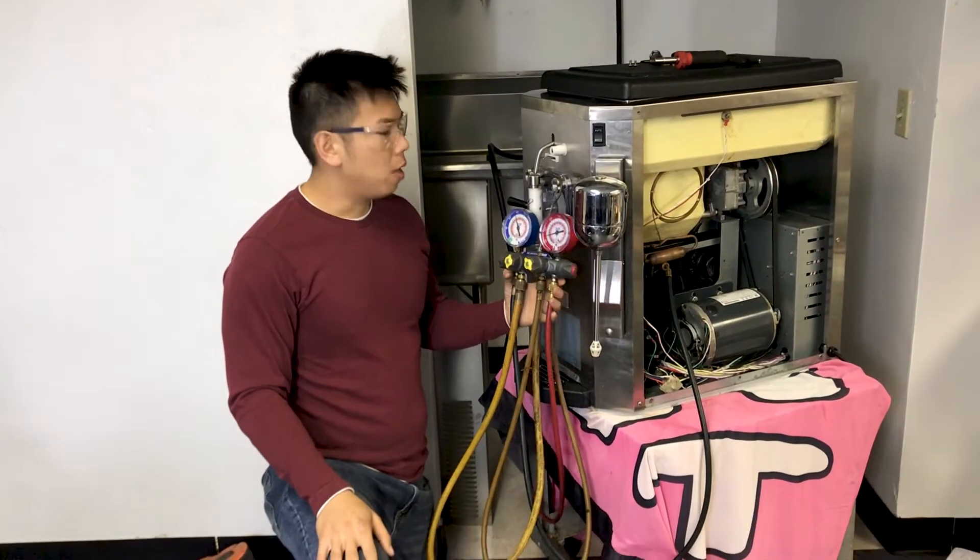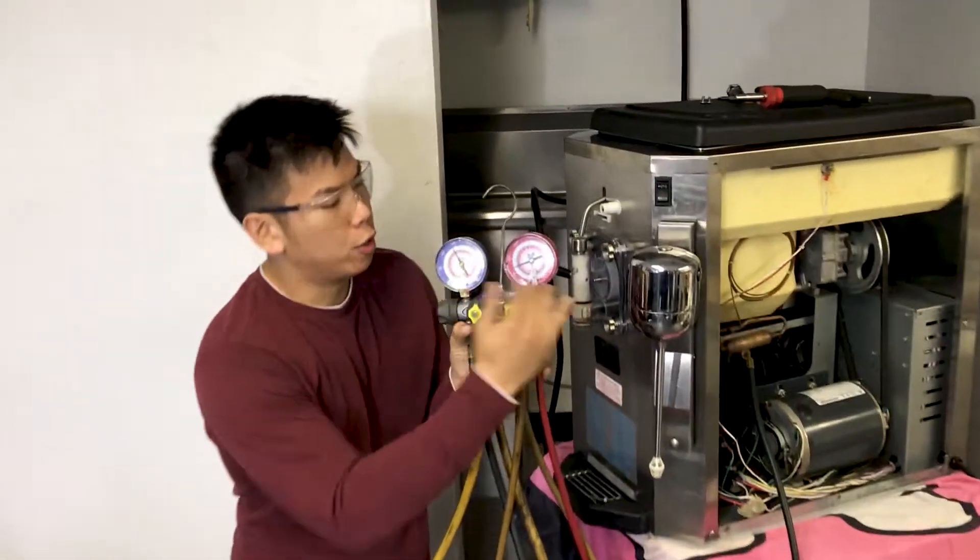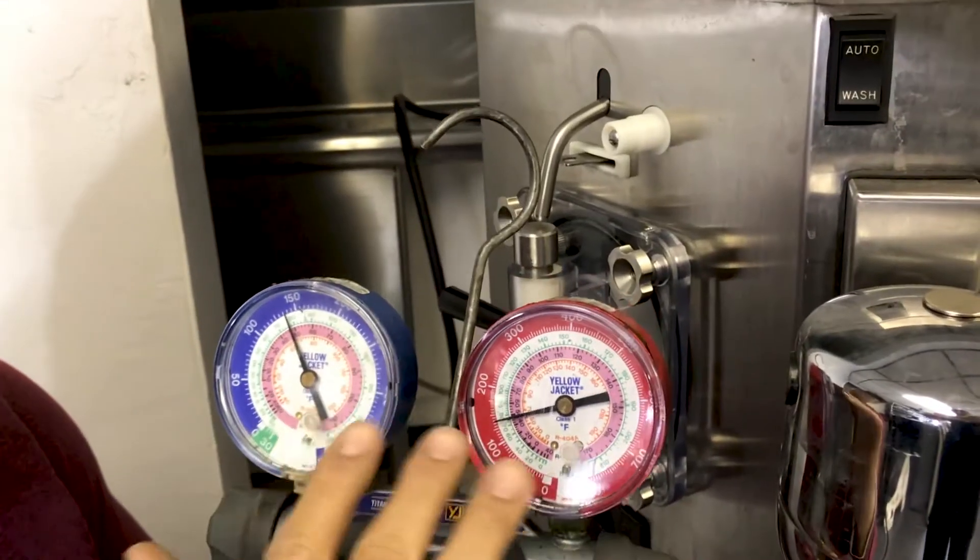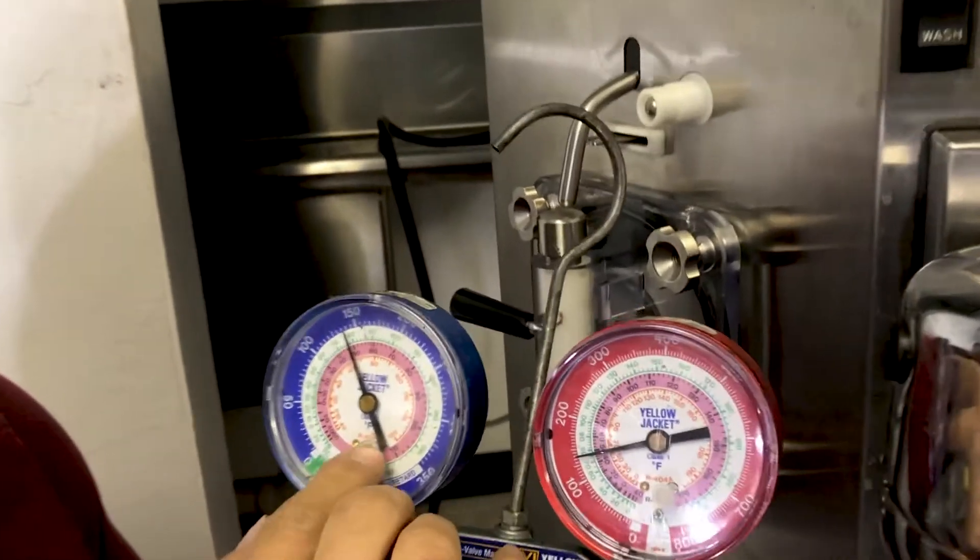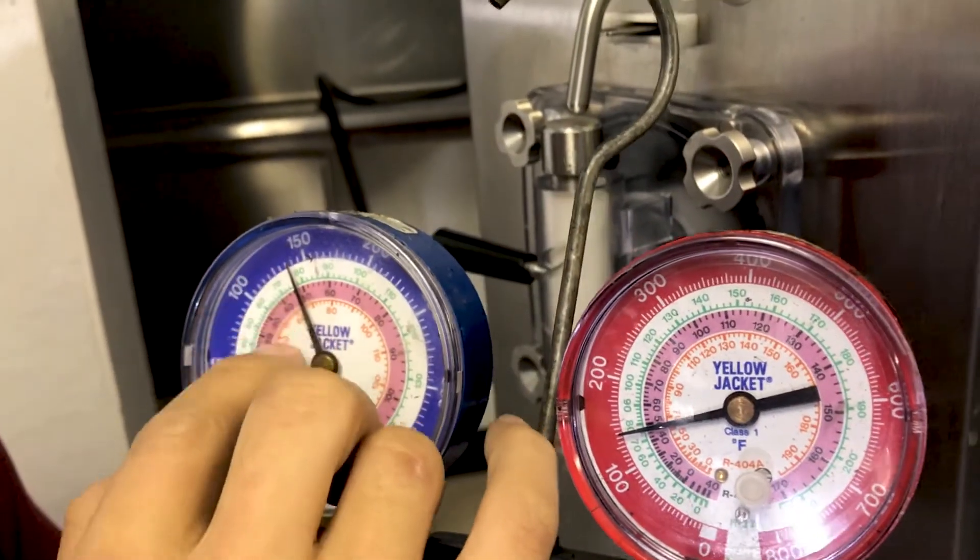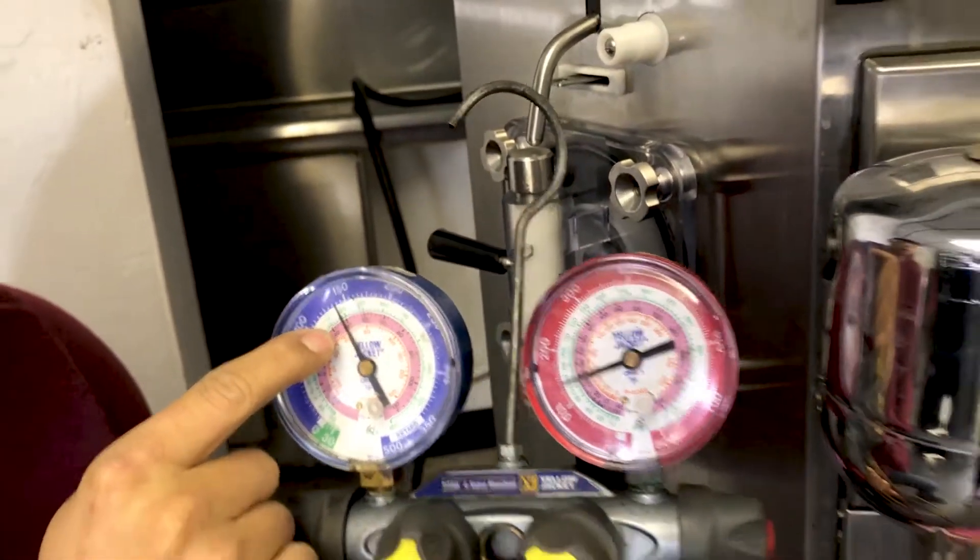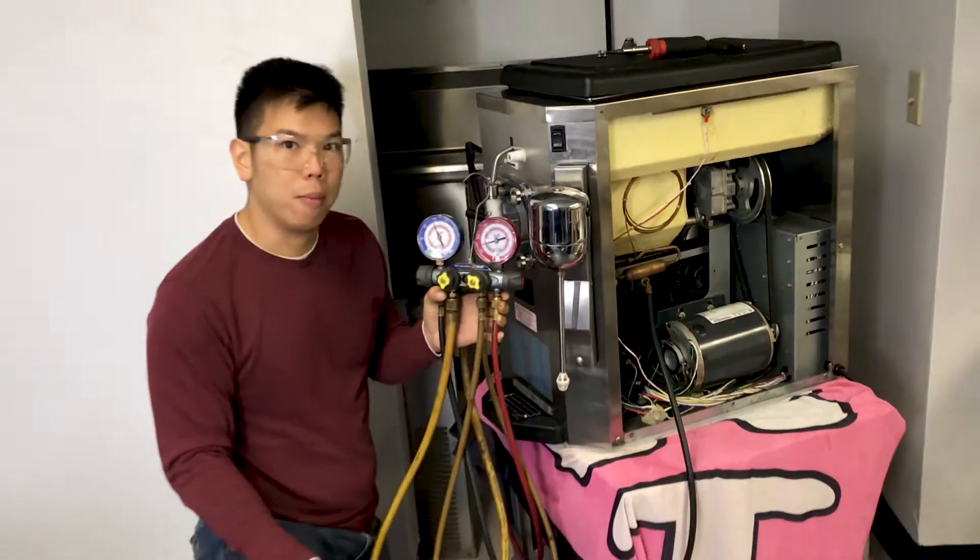Alright, once you have your gauges hooked up with the machine not running, you want to make sure your static pressures are around this. So our ambient temperature here is around high 60, low 70s right now. So if you look at the 404 section here, it looks about right because the pressure is around 140, and it correlates with the temperature of what it would be at for 404A. So from here, you turn on the machine, and we're going to check the running head pressures.